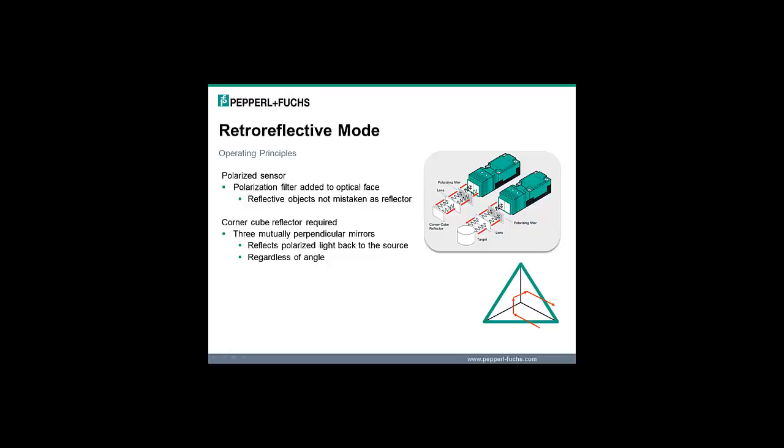Nearly all modern retroreflective sensors are polarized. Using the same concept manufacturers of sunglasses use to lessen the harmful effects of ultraviolet light, polarized retroreflective sensors have a horizontal polarization filter added to the sensor's optical face. The goal is to ensure that very reflective, mirror-like objects are not mistaken as the reflector. The process requires that a horizontal pole filter be placed over the emitter and a vertical pole filter be placed over the receiver — so that shiny surfaces, like a shiny aluminum can, are not mistaken for the reflector.